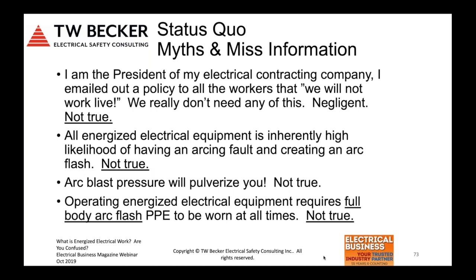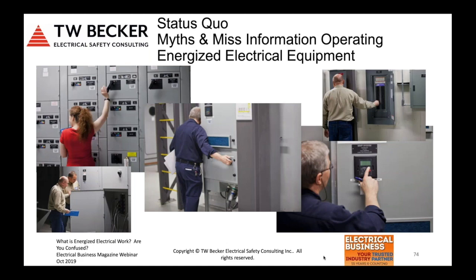The last one, which was the poll question: operating energized electrical equipment requires full body arc flash PPE be worn at all times. That is not true. This is where, again, risk assessment and the risk assessment procedure identified in Z462 and 70E is a useful tool to get you to understand when a worker is exposed and when they're not exposed to arc flash and/or shock. So here are pictures of operating with no PPE. Following procedure: stand to the side, look away, standard procedure, use the right hand. The left hand rule is not a legal requirement, and in my opinion was never a valid method. Use the right hand, look away, again for the unlikely probability that you're going to get an arcing fault and arc flash when you switch these disconnect switches, or when we're using an HMI on a VFD or a control panel.